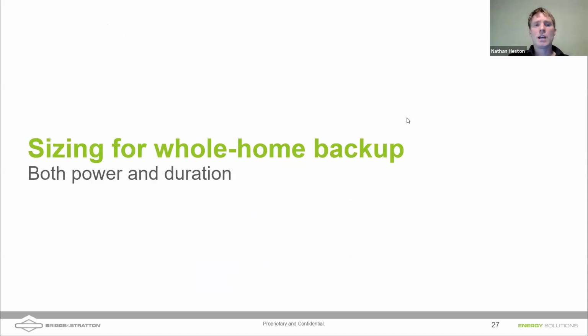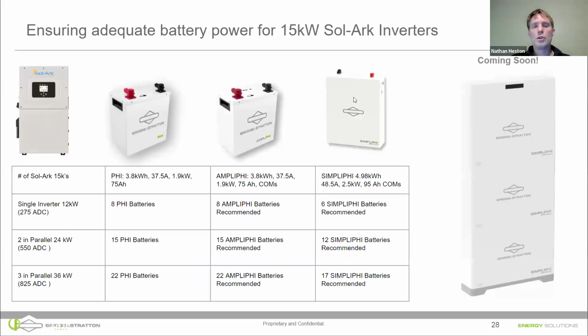Let's talk a bit about sizing for whole home backup. There are limitations on batteries with both how much capacity they have, and everybody knows, right? That's the size, the number of kilowatt hours your battery bank holds, the size of the gas tank. But there are also power output limitations of batteries, and this refers to the C rate of the battery. So a C rate of 1 would mean your battery can charge and discharge safely without damage in 1 hour. Our batteries are rated at C/2, meaning that these batteries can charge and discharge in 2 hours. I will note that the new battery shown on the right side of the screen is considerably faster, charging and discharging much quicker than the C/2 of the batteries we have here.